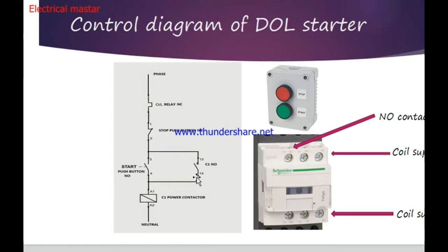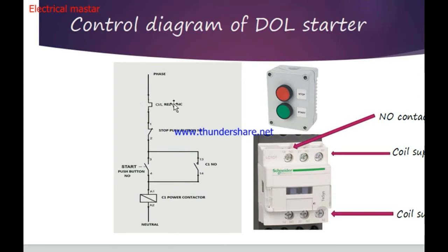If the motor is overloaded, the overload relay — already connected to the motor — has a set point at 120% of full load current. When the overload relay activates, its NC contact opens. Since the NC contact is open, the control supply is cut. The phase supply is interrupted, the magnetic contactor de-energizes, and the motor turns off. This is how the overload relay saves the motor. This is the main control operation of DOL Starter.